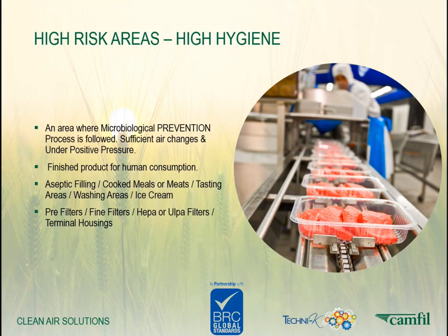High risk areas are high hygiene, which is an area where a microbiological prevention process is followed. Sufficient air changes are achieved and the area is kept under positive pressure. Examples of this are finished products for human consumption, aseptic filling, cooked meats, tasting areas, washing areas, or ice cream production. The same pre-filtration as basic care areas should be followed. Second stage filters should again be at a very minimum F7 or ePM1 50%. Final filters in these areas will be HEPA or ULPA, depending on the application.